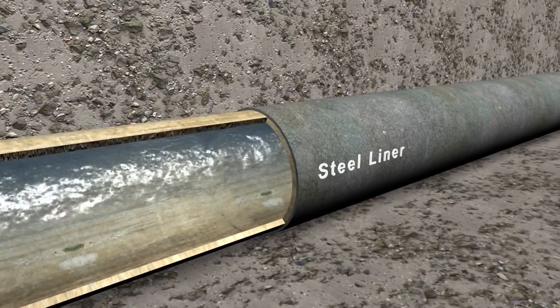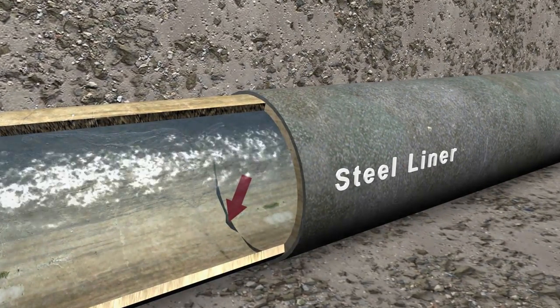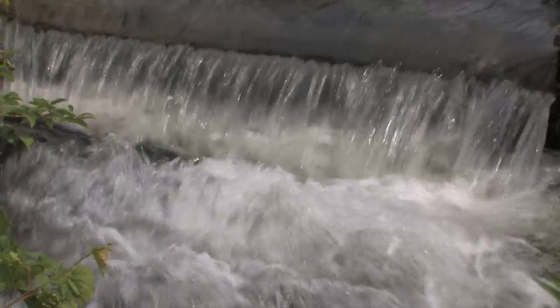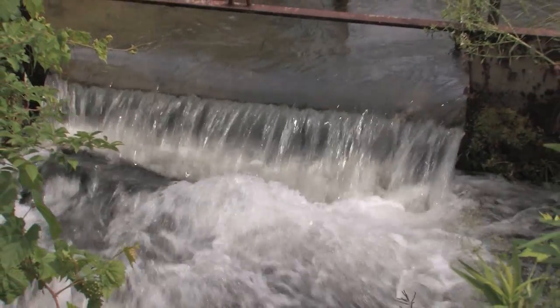But over time, some cracks developed at the ends of the liner and began leaking water. Engineers have determined that the Delaware aqueduct is currently leaking up to 35 million gallons of water a day in Wawarsing and Roseton collectively.